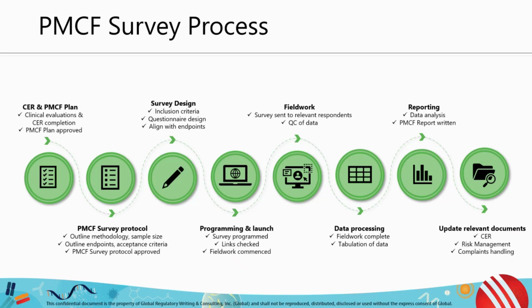But if we start on the left-hand side here, you'll see that you're doing PMCF data because your device is on the market. So you'll have a clinical evaluation report completed. You'll then start needing to identify any gaps in that documentation and feed that into a PMCF plan. If your PMCF plan suggests that a survey is an appropriate method, you're going to need to then move on to thinking about your survey protocol or your survey plan, which should outline the methodology and the sample size. It should outline endpoints and acceptance criteria. And then what you can do is feed that into your actual survey design.